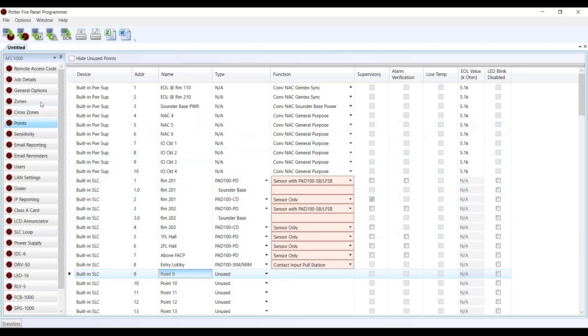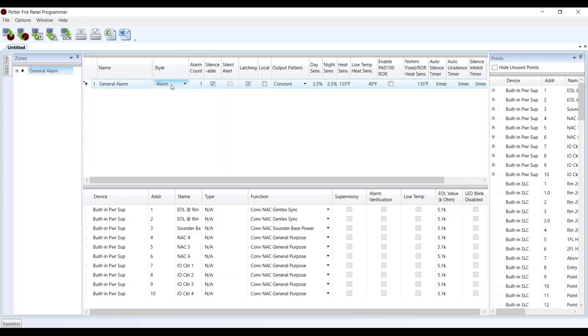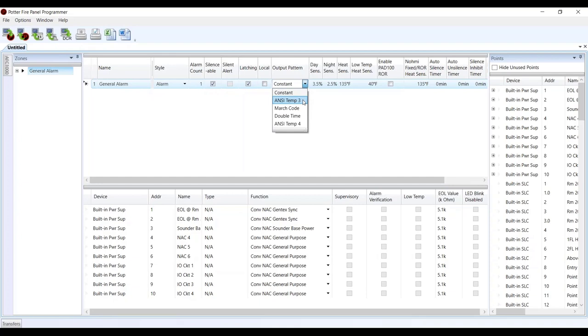Let's jump over to the zone screen. Zone 1 will be our general alarm. Make sure you name your zones — the zone name displays on the panel when a point goes into alarm in addition to the point name, so don't leave it as zone 1, zone 2. The style is going to be alarm, silenceable, latching — standard for general alarm. The output pattern here determines the pattern on your sounder bases, so we're going to change that to temporal 3.